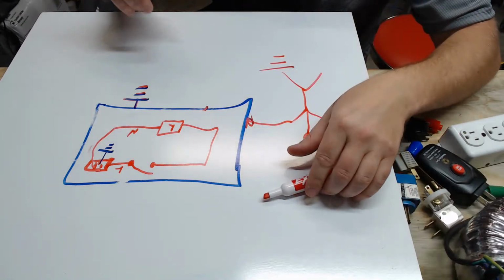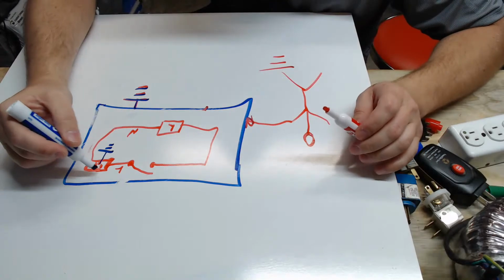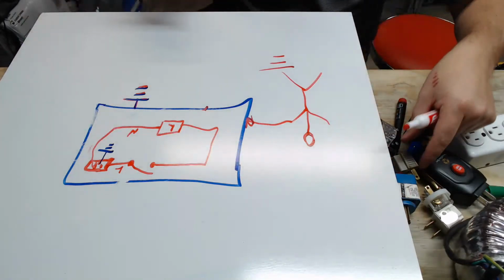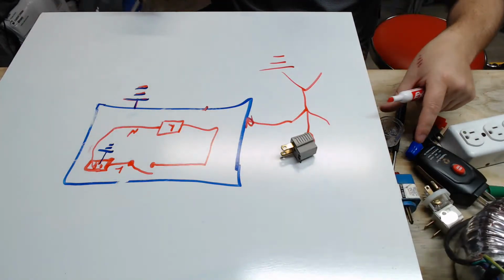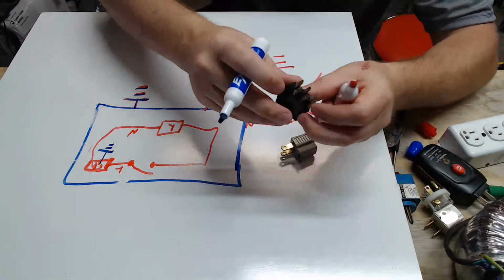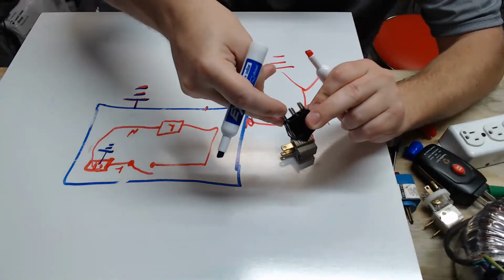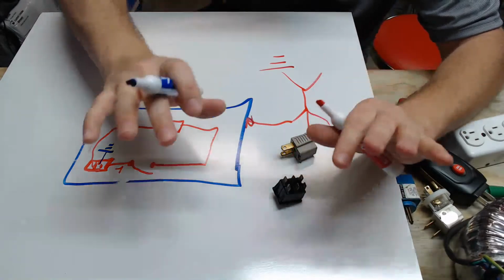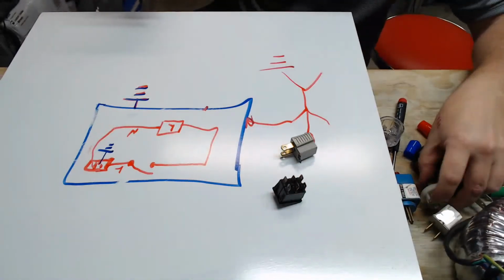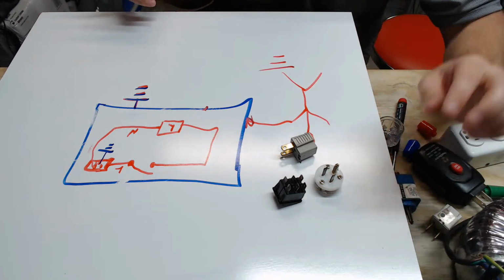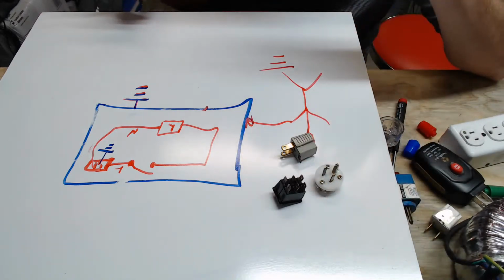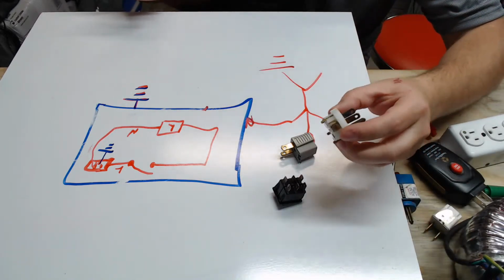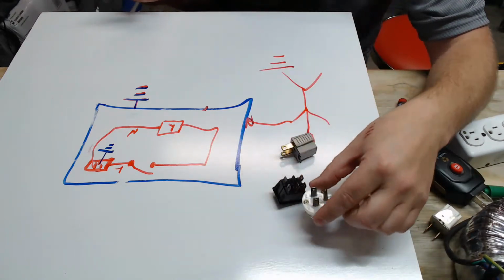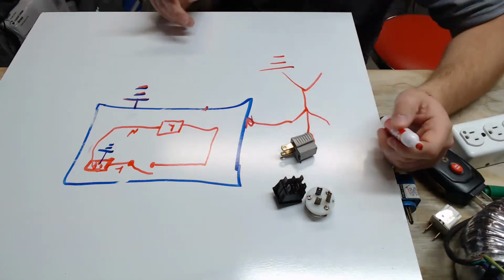Now imagine this. Imagine that we reverse the polarity of your plug end, or on the inside of the device, you accidentally flip these two wires around. It can and does happen, guys. That's why I'm saying always disconnect wires and reconnect them exactly to the same exact poles that you disconnected them from. Let's say you wired this guy wrong when you put a cord together.